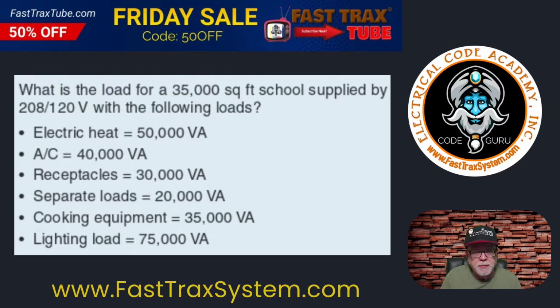Hopefully you're doing this with me. And that gives me 210,000. So write that down, 210,000. Now, since we know the overall VA, that is the total, we're using that as our total connected load. Again, we did not use the AC because we took everything and we took out the AC, because it says in 220.86, take the larger of heat or AC. So that's how we got 210,000.